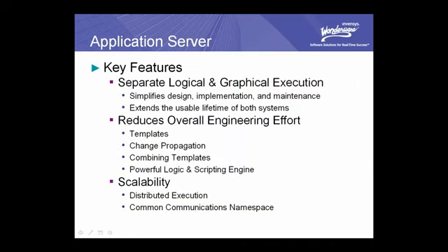So far, we've only focused on these templates that are relatively simple representations of our real-world devices. But another benefit of these application templates is how they can be combined to represent more complex devices and equipment. Here's an example of a brew kettle, which contains other templates for things like valves, pumps, motors, agitators, and a whole lot more. And this template is used to create instances that represent real-world equipment, like 2 brew kettles actually used in production. And if we need to add another brew kettle to the process, our supervisory system and HMI can be updated by simply right-clicking on the template and selecting New Instance.